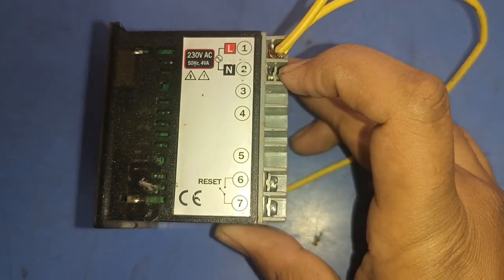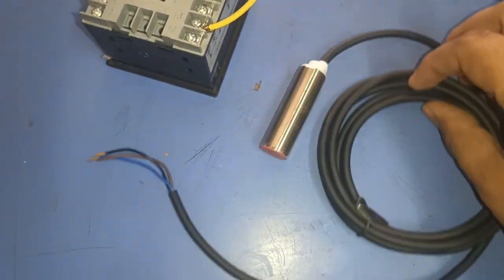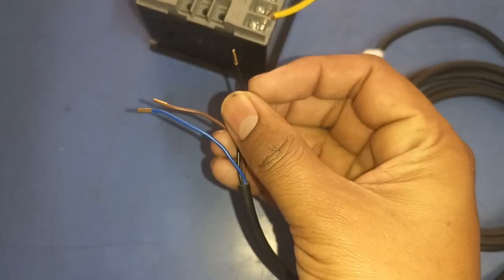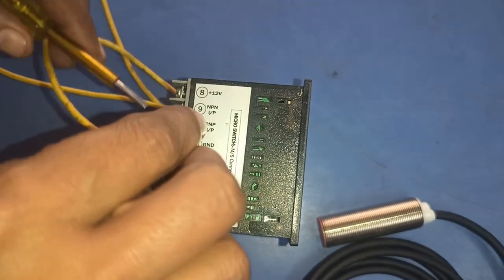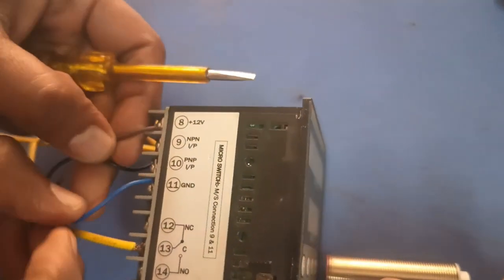Connect the neutral wire to terminal number 2. For sensor connection, this is a PNP type sensor with three wires: brown wire for positive power supply, blue wire for negative power supply, and black wire is the signal reference. Connect the brown positive wire to the plus 12V supply at terminal 8, the blue wire to ground at terminal 11, and the black PNP signal wire to terminal 10. If you have an NPN type sensor, connect it to terminal 9.